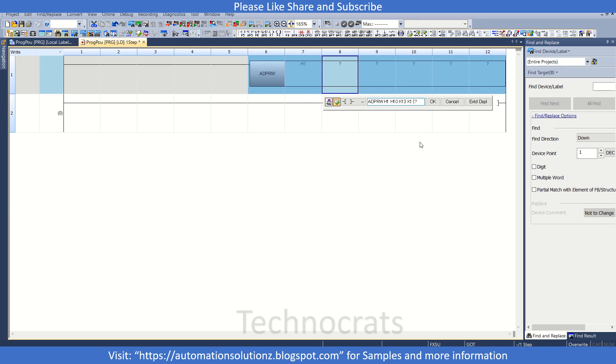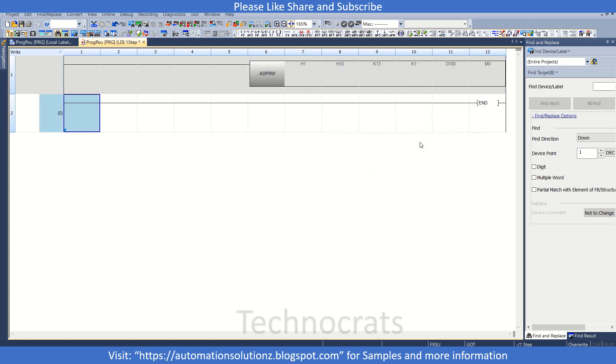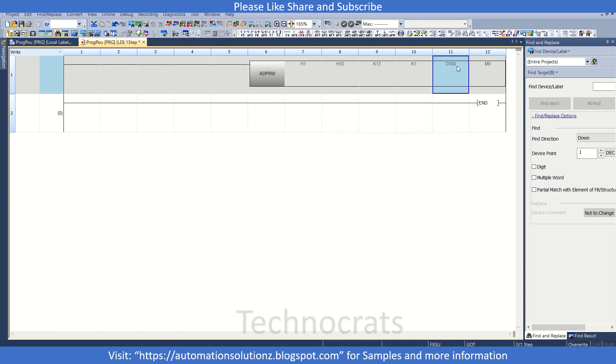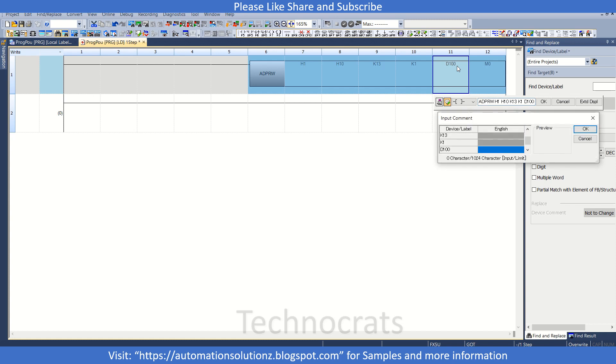Now the number of devices I want to write is K1. The data register which I will write is D100. I will add the value of D100 to register number 13. And here we have this M0 bit, that is for the status of ADPRW instruction.